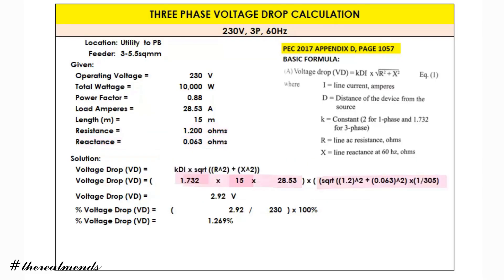After using your calculator, you can arrive at an answer of 2.92 volts. To get the percentage, simply divide 2.92 by 230 and multiply by 100. The voltage drop percentage is 1.269 percent. Notice that this is less than 2 percent, which means the conductor we used is within the 2 percent allowable voltage drop based on PEC provisions.